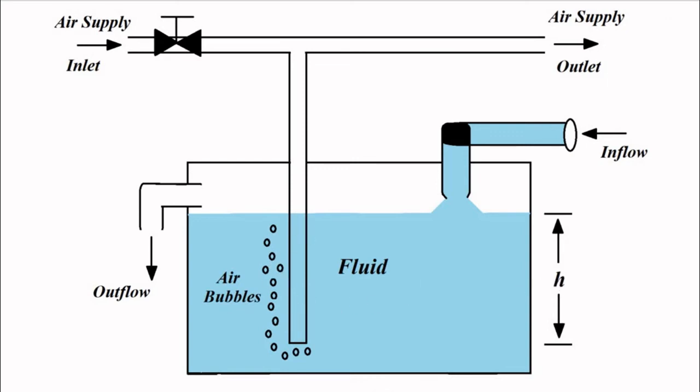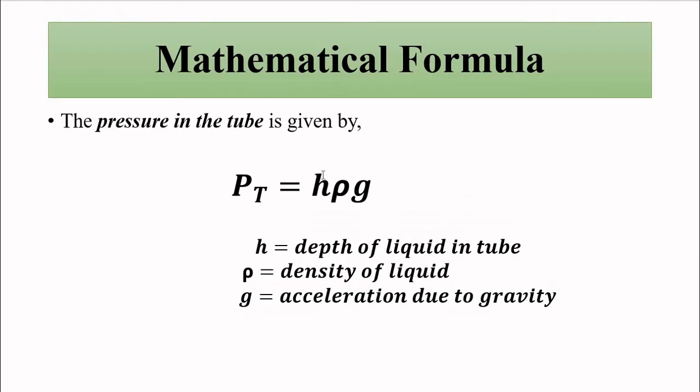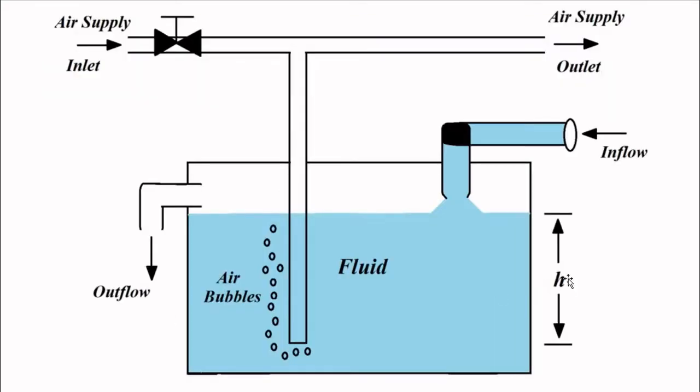The pressure generated by the air bubbles in this much portion h of the tube, height h of the tube, is given by h*rho*g. The important thing is that this h is fixed because level is maintained fixed in the container with the help of level measurement techniques.